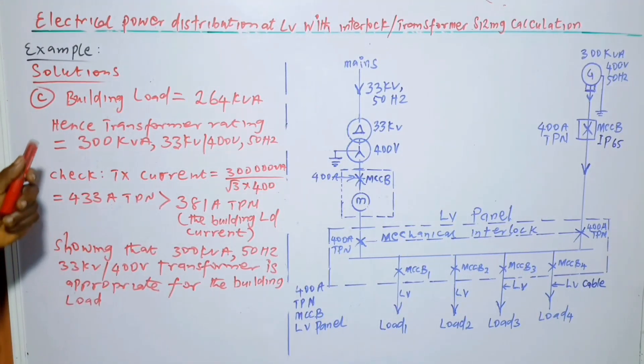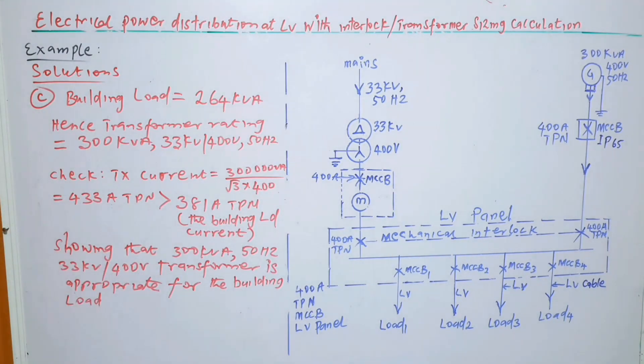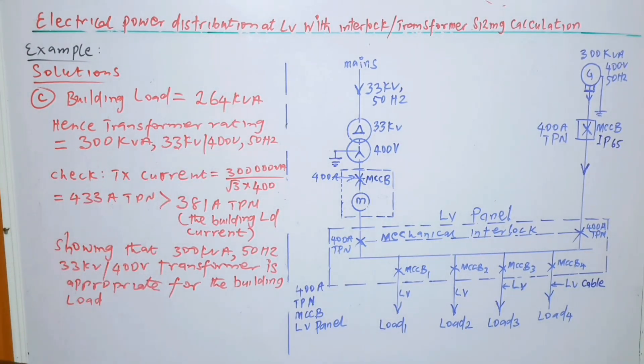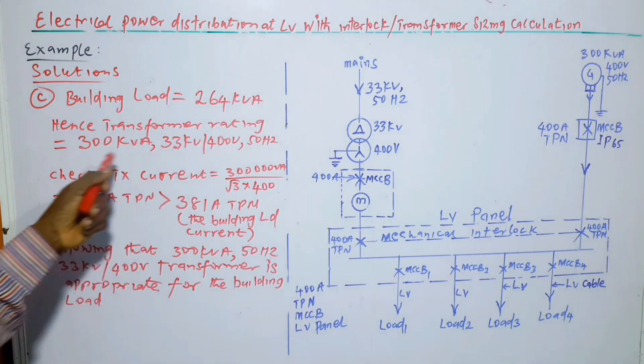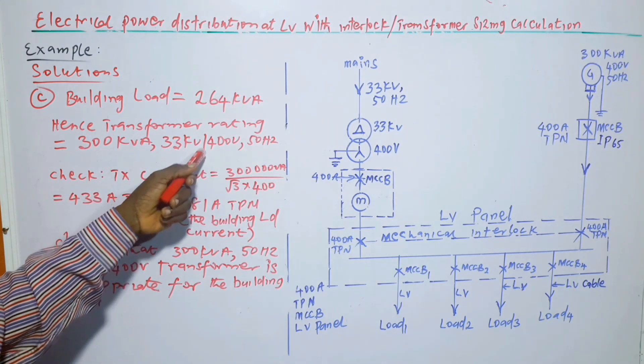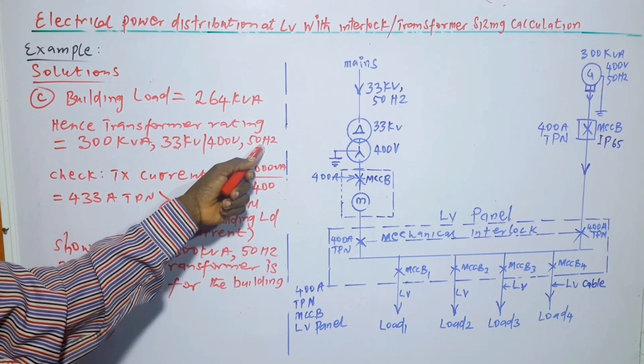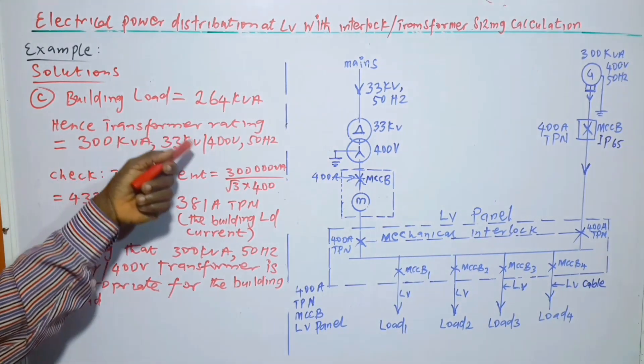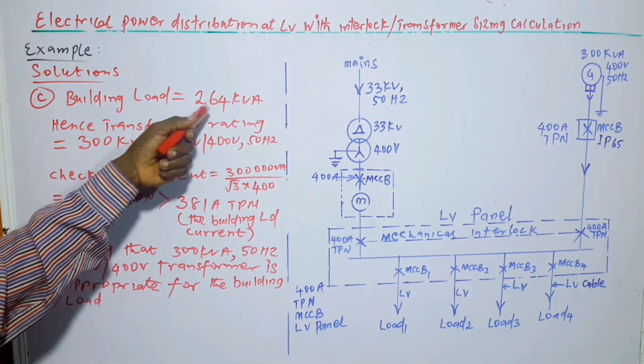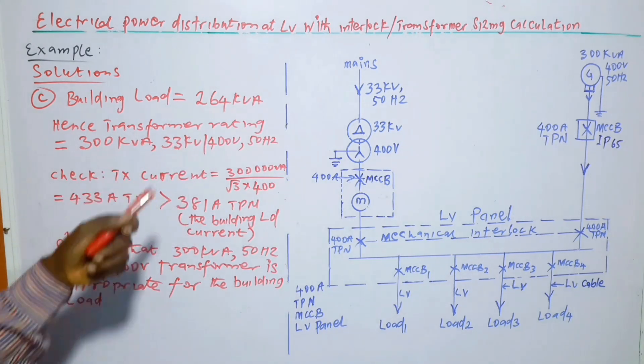Moving on, C part. To calculate the transformer rating, building load is 264 kVA. Hence, transformer rating is equal to 300 kVA, 33 kV slash 400 volts at 50 hertz. So we choose the transformer rating that is higher than the building load. So the next one is 300 kVA.